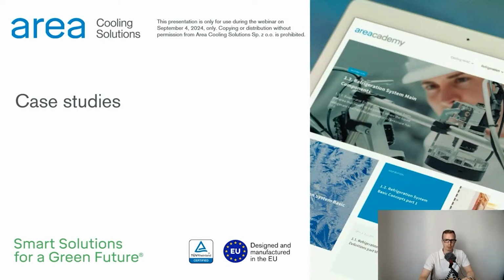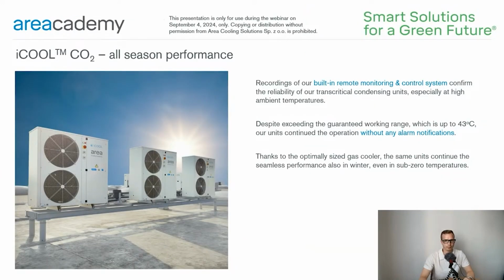Now let's move on to some case studies of installations working with iCool CO2 units. Our iCool CO2 transcritical inverter units are designed for all seasons operations. These units can operate efficiently both during the winter, when the ambient temperature is well below 0 degrees Celsius, and also during the heat waves, when the ambient temperature reaches above 40 degrees Celsius. Recordings of our built-in remote monitoring and control system confirm the reliability of our transcritical condensing units, especially at high ambient temperatures.